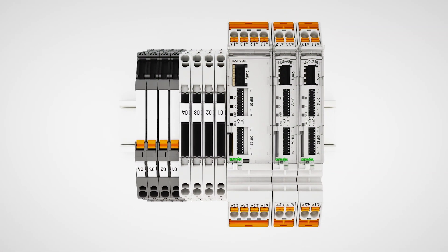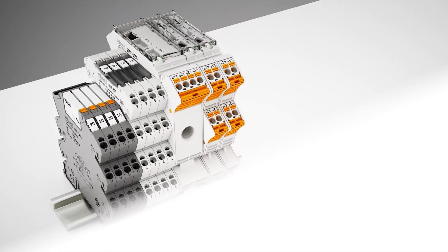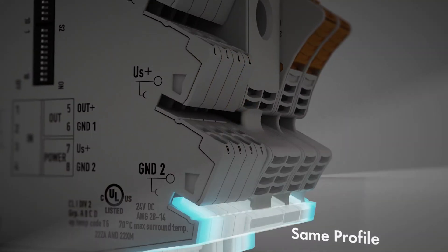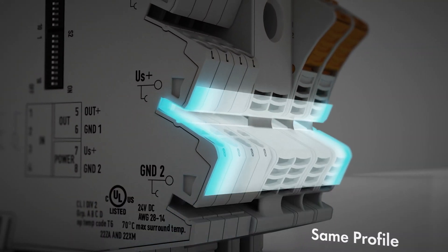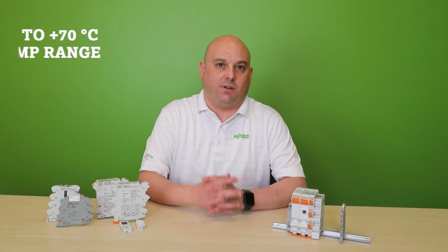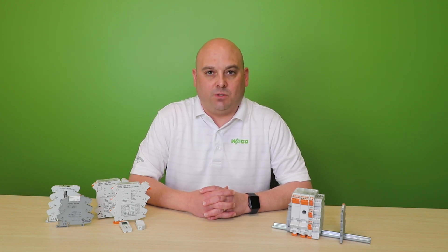Our conditioners come in two different styles. The first is the slim style space-saving 857 series. You might notice that these devices share the same profile as our 857 relays, which allows for convenient jumpering. Other benefits include a minus 25 to plus 70°C temperature range, 2.5 kV of isolation, and dedicated and settable versions.